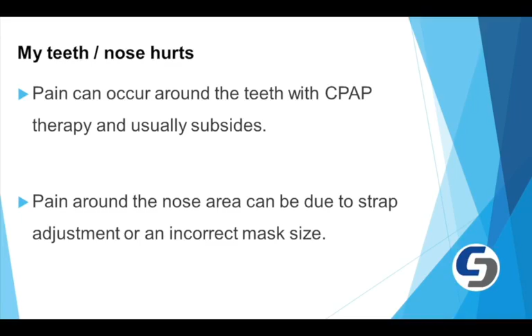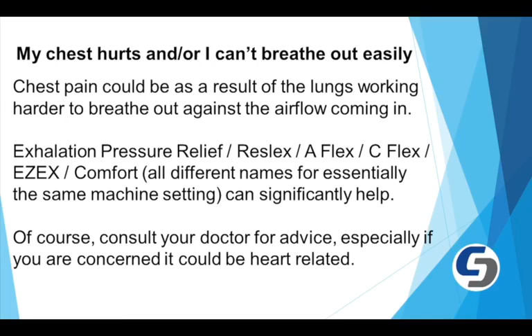Chest pain could be as a result of the lungs working harder to breathe out against the airflow coming in. Now, exhalation pressure relief, or ResMed's EPR, Philips' Flex, C-Flex, EasyBreathe Comfort, these are all different names, but essentially the same machine setting, and this can significantly help. Pressure relief reduces the airflow when the machine detects that you're breathing out and lowers the incoming pressure accordingly. Typically settings are 0 to 3, 0 being off, and the higher the number, the easier it will be to breathe out. And this setting can be very helpful for patients using nasal pillow masks. So consult with your support team for advice, and remember again, support is your key to successful CPAP therapy. Just one point really, if you do have these chest pains, of course consult your doctor for advice, especially if you're concerned that it could be heart related.